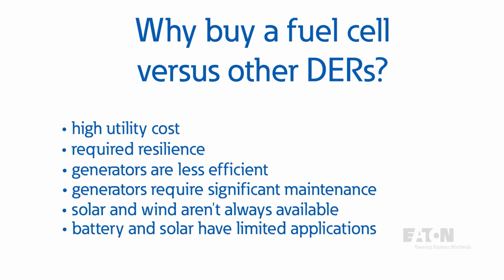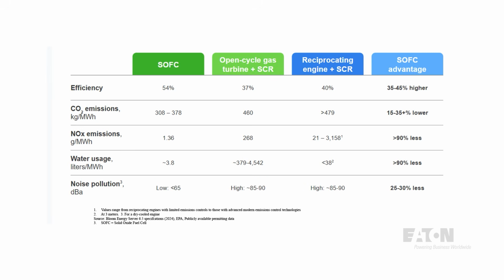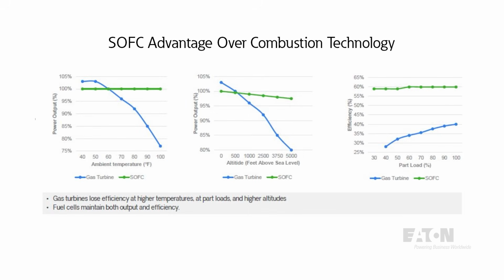Solar and wind are good options as part of a microgrid, but aren't always available. Fuel cells don't rely on the sun or the wind. Batteries are great for short demand management in high-cost utility areas, but don't provide long-term outage protection or long-term demand reduction or base load reduction. In addition to these benefits, fuel cells have other advantages over more traditional energy sources. Specifically, considering a natural gas turbine, the ambient temperature, altitude of the installation, and the loading of the unit affect the output power much less on a fuel cell than a generator.